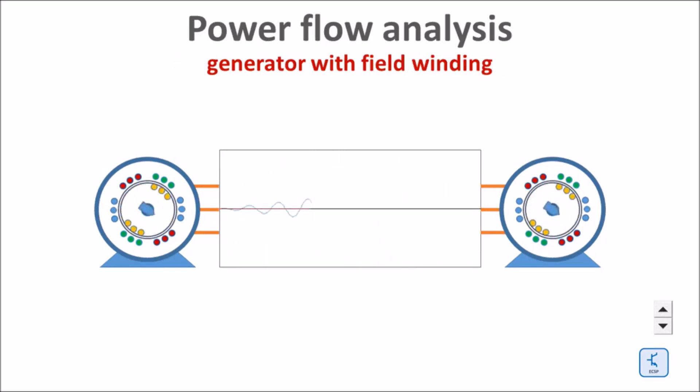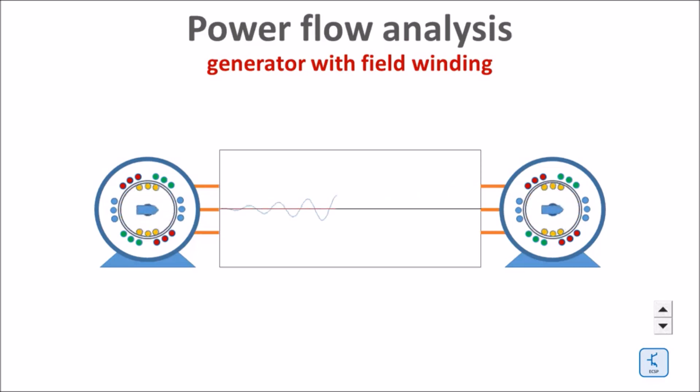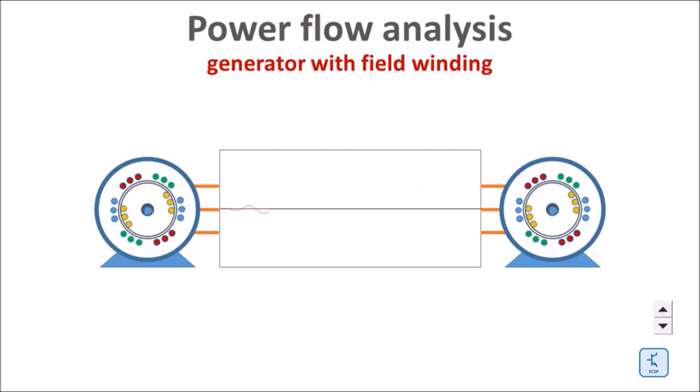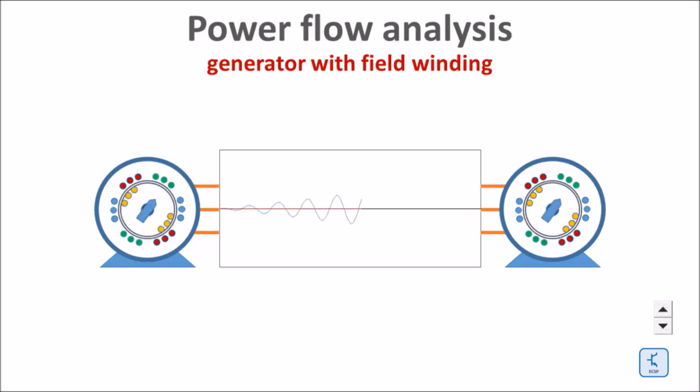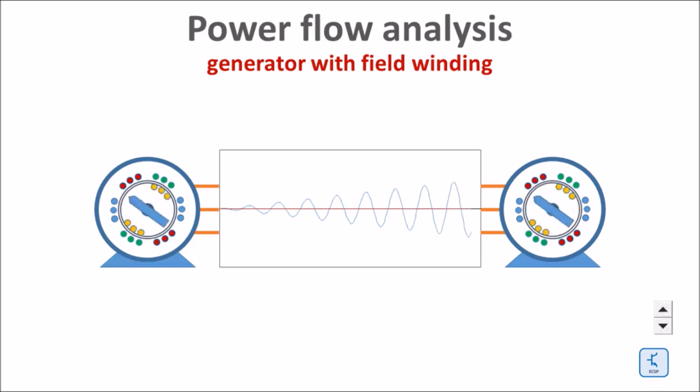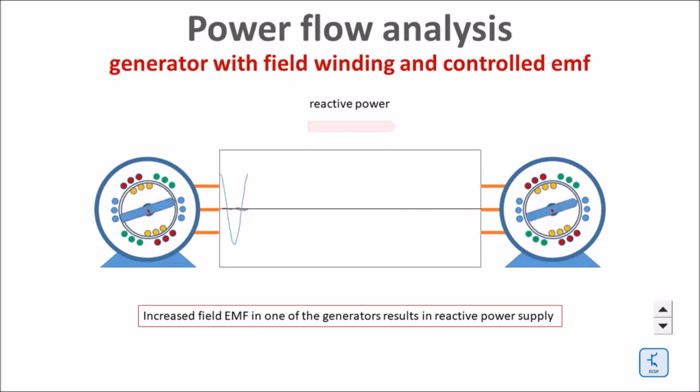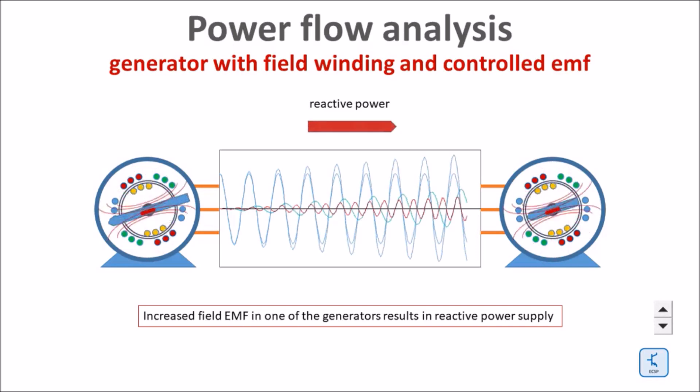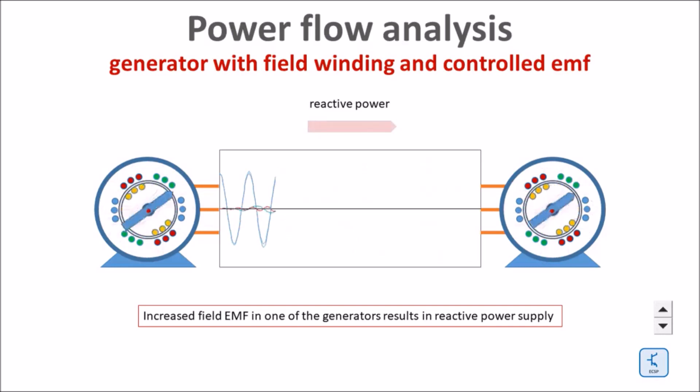Larger synchronous generators do not have a permanent magnet in the rotor but a DC coil powered by a DC source. The result is a rotating magnetic field as well, but controllable. Look at the blue rotating arrow. The AC output voltage is a function of the excitation DC current in the rotor. If the rotating DC field in one of the two generators increases, the induced voltage in one generator will increase as well.